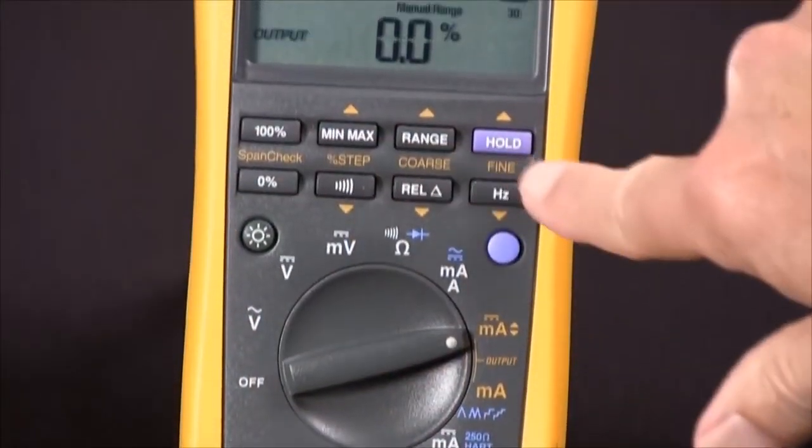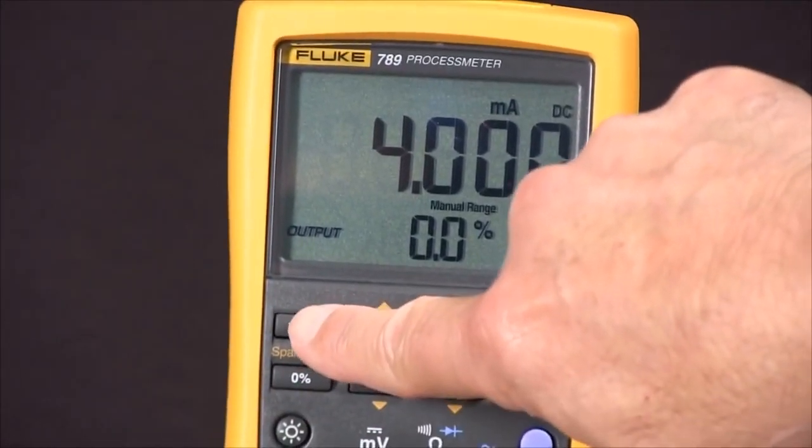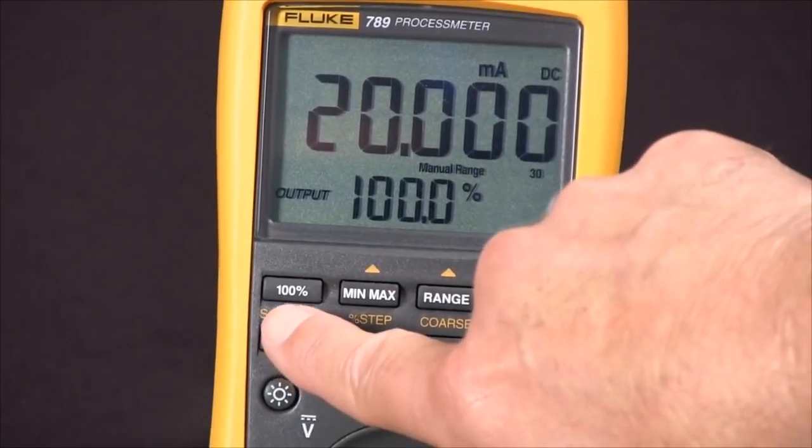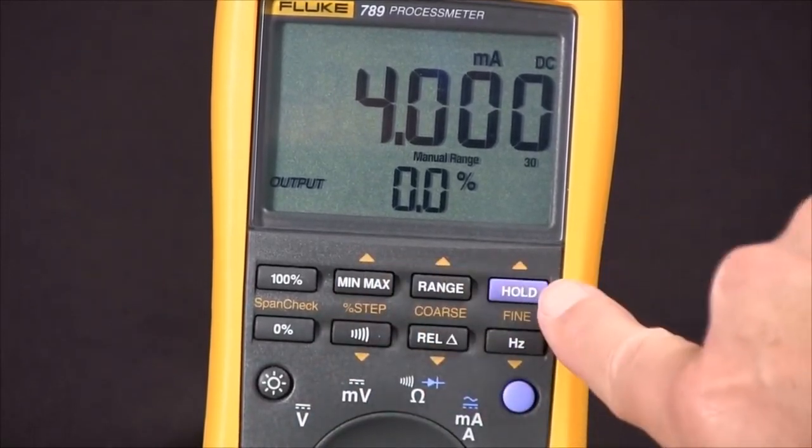We can start over here with the span check and we can go from 0% of span to 20 milliamps, or 100% of span, or zero. And then with these three we can do 25% of span coarse or fine adjustments.